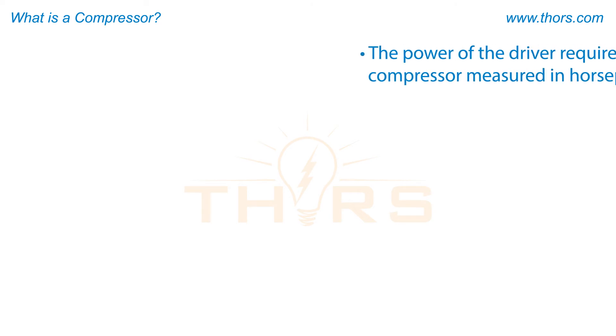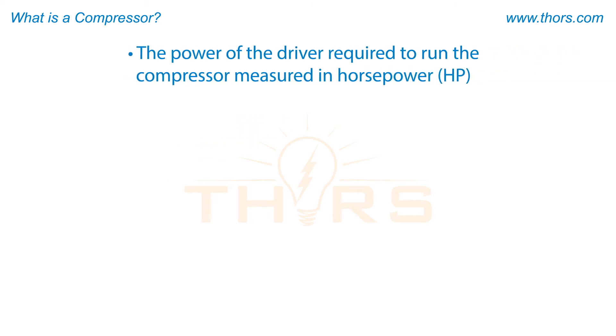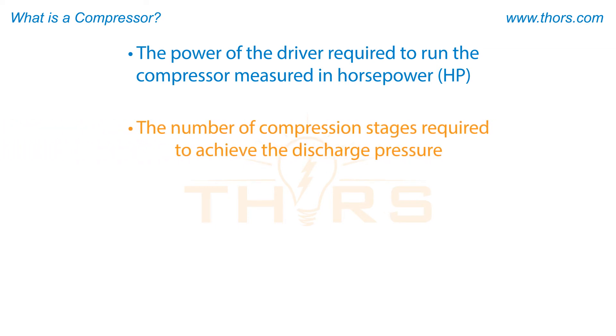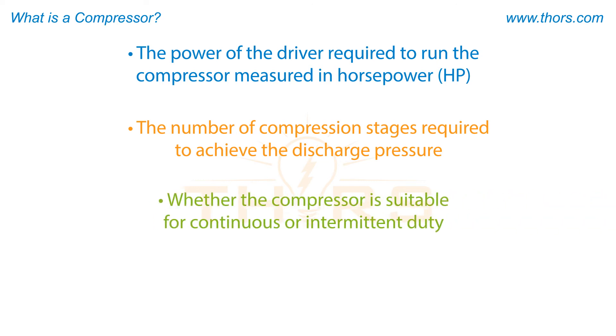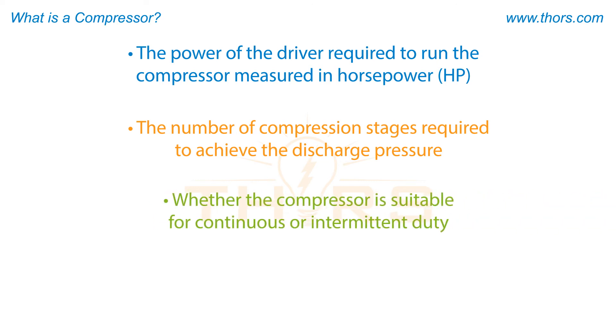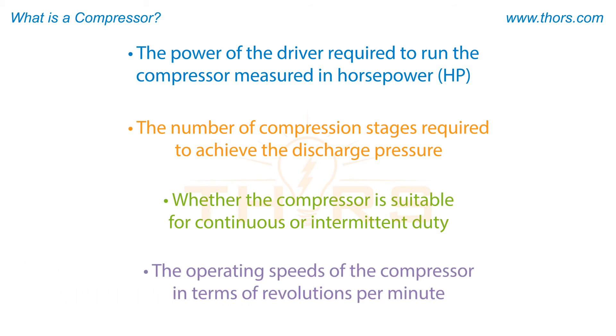Other important specifications include the power of the driver required to run the compressor measured in horsepower, the number of compression stages required to achieve the discharge pressure, whether the compressor is suitable for continuous or intermittent duty, and the operating speeds of the compressor in terms of revolutions per minute.